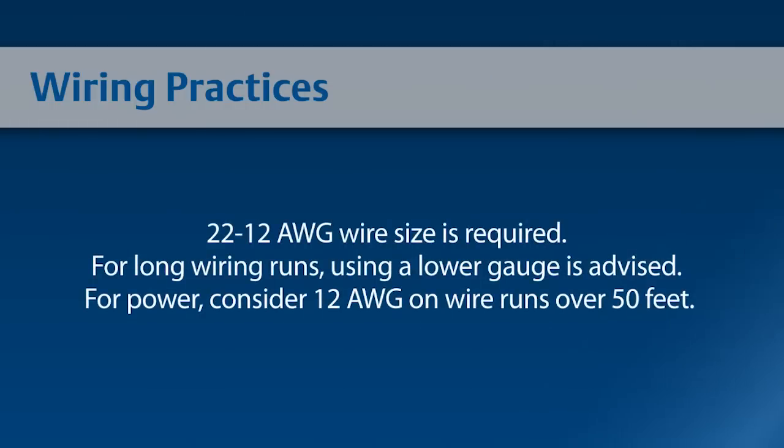22 to 12 gauge wire size is required. For long wiring runs, using lower gauge wire is advised. For power, any wire over 50 feet should be 12 gauge.